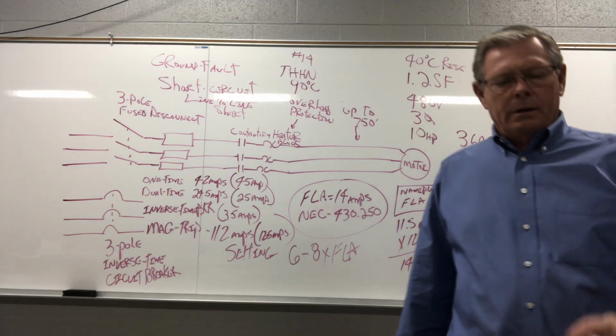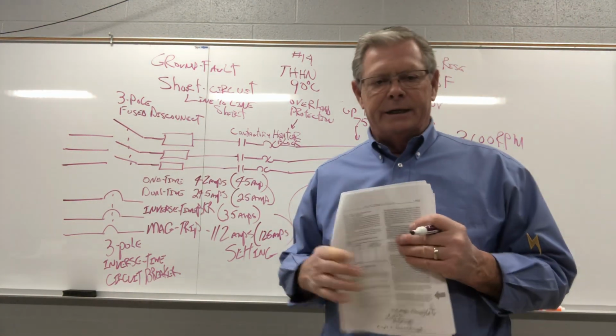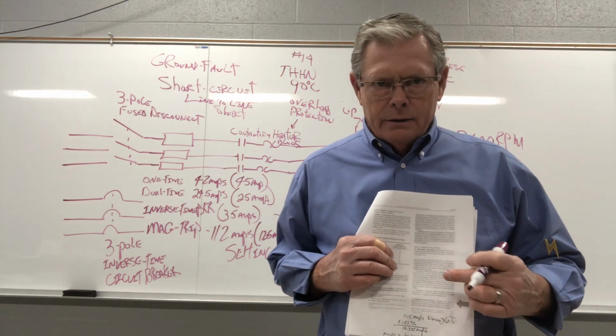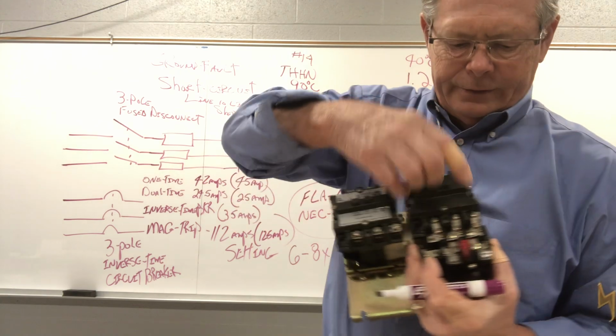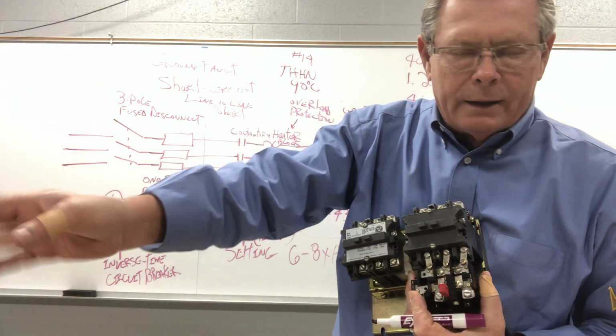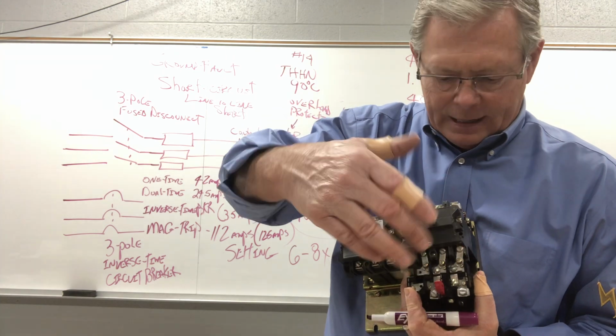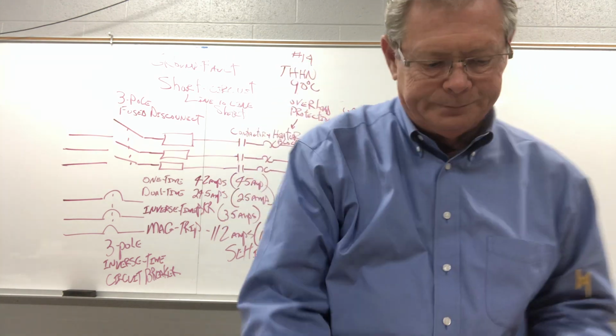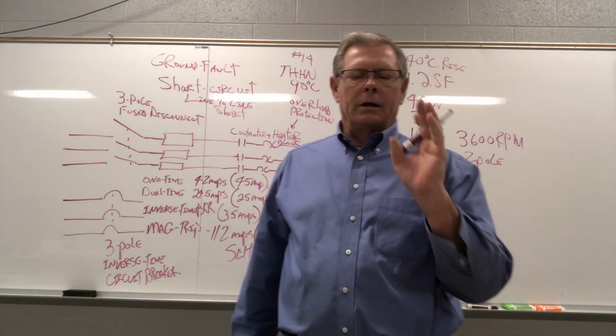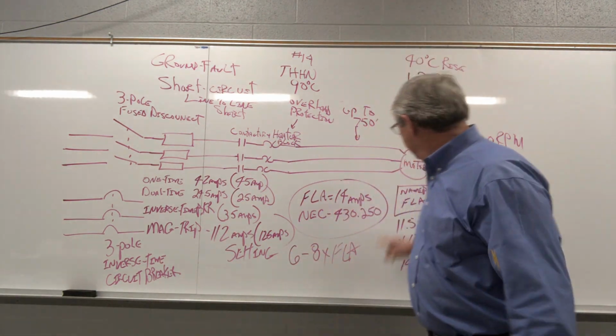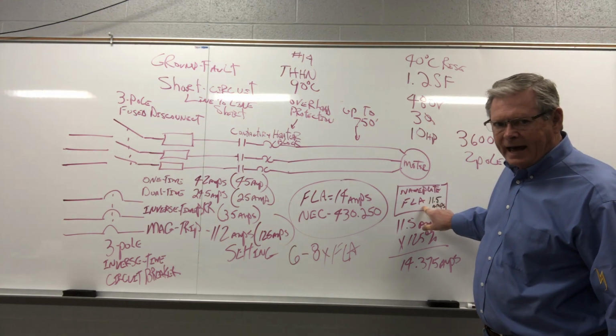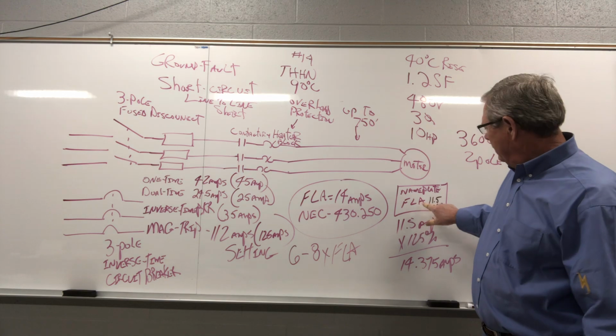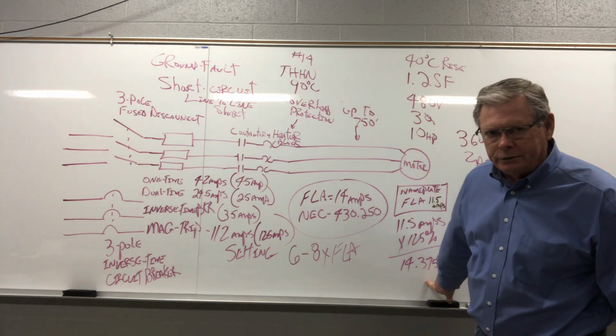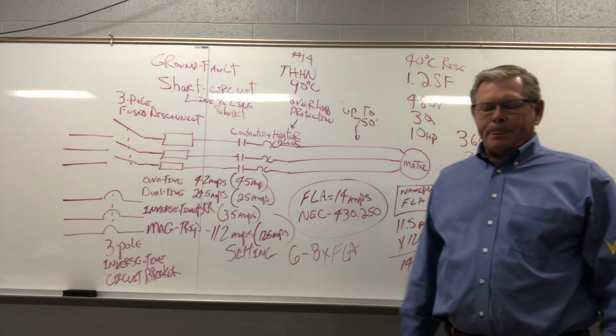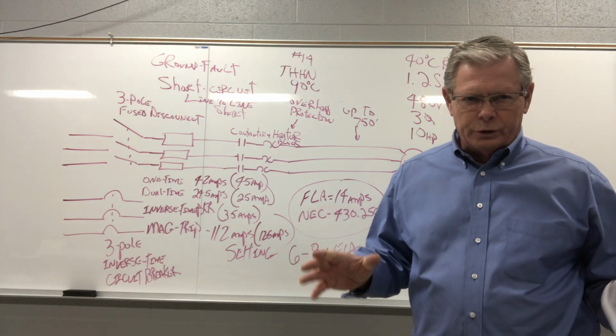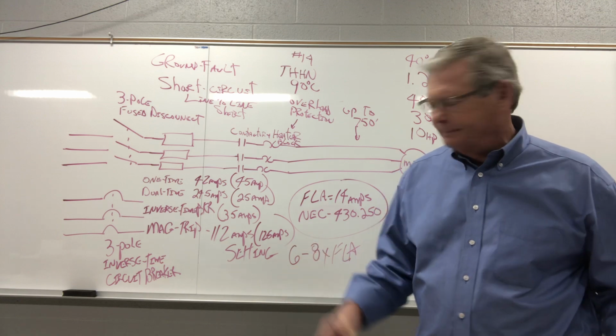Now, the code says that we select motor heaters because these 3 little things here, we unscrew, pull them out, you get 3 of the right ones and put them in. And that custom fits this to your motor. Most electric shops will use nameplate current. They'll use 11.5 amps. This is so important, so important. 11.5 amps when they should be using 14.375. Now most equipment is over-engineered, which means you got more horsepower than you need, okay?